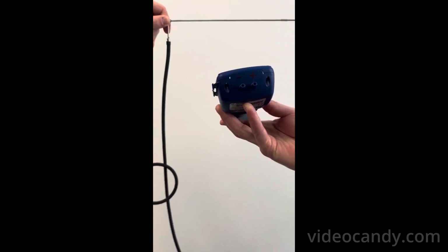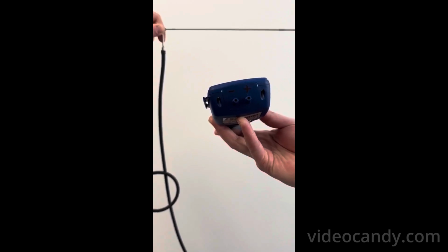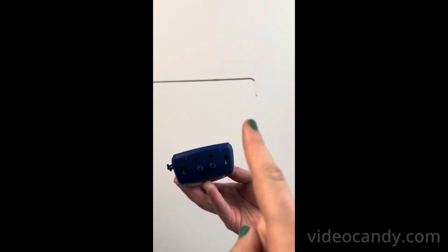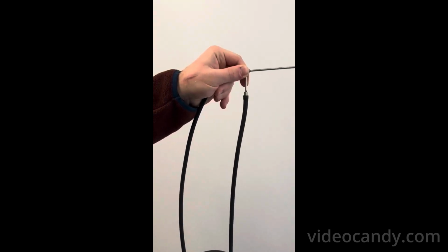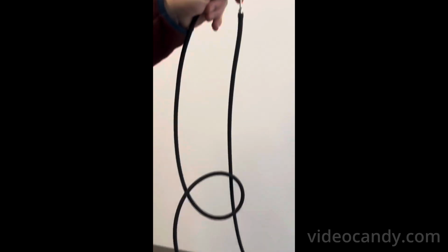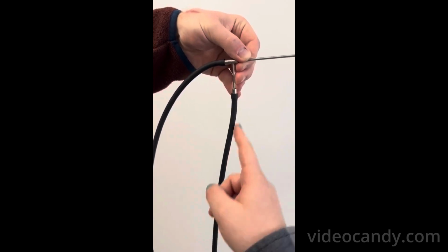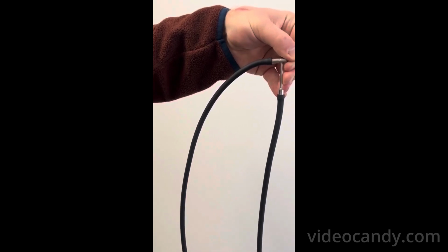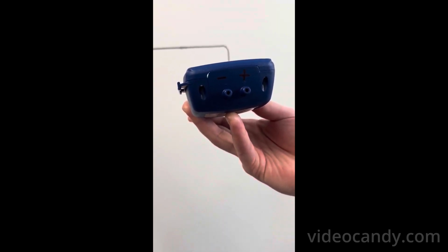Let's take some measurements of static pressure, velocity pressure, and total pressure. In order to take these measurements, you're going to need a pitot tube. This end of the pitot tube is going to be put into your fan. And over here, we have two different areas where you'll have tubing coming off from. This first one is going to measure the wall pressure, and this one over here is going to measure the pressure inside the duct.